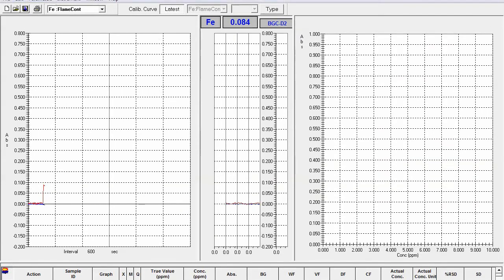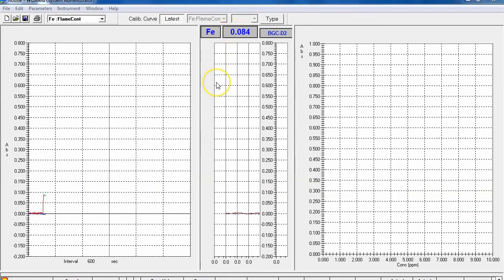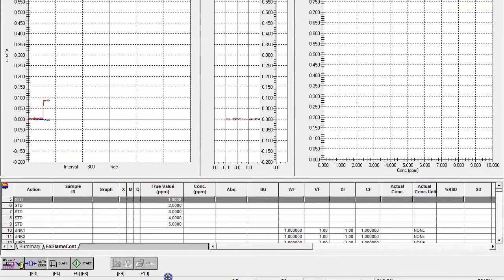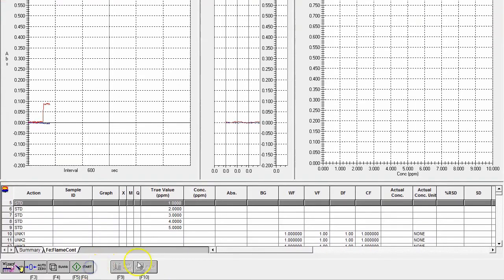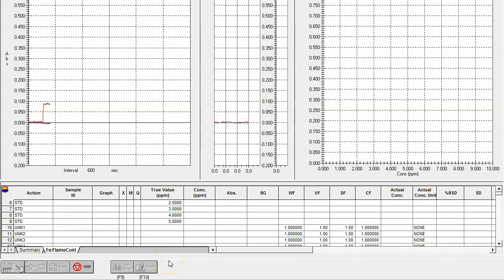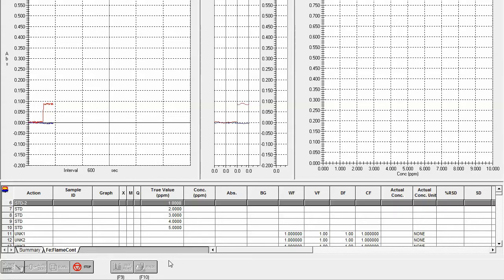And you'll see pretty quickly, if I scroll back up, that the number up here is changing. So that's increasing as our iron standard is being taken up by the machine. Now we're going to hit start down here. What it's doing now is taking those 3 measurements that we set it up to take. Remember, we did spray, measure, measure, measure. So it's spraying the sample into the machine and taking 3 measurements.